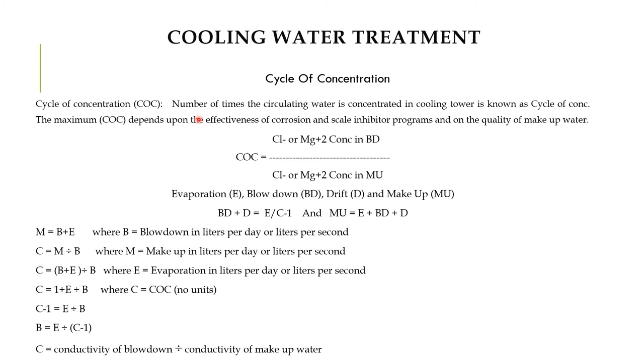Cycle of Concentration (CoC): the number of times the circulating water is concentrated in the cooling water system is known as the Cycle of Concentration. The maximum CoC depends on the effectiveness of corrosion and scale inhibitor programs and on the quality of makeup water added. CoC = chloride or magnesium concentration in blowdown ÷ chloride or magnesium concentration in makeup water. It also depends on evaporation (E), blowdown, drift loss, and makeup.